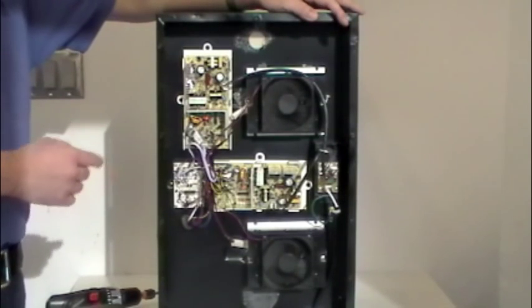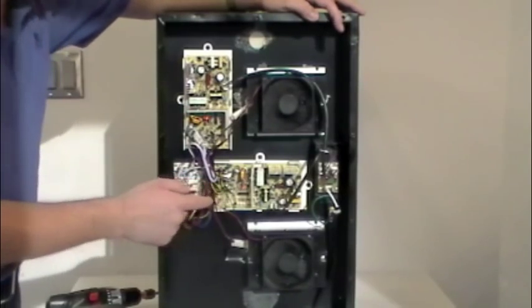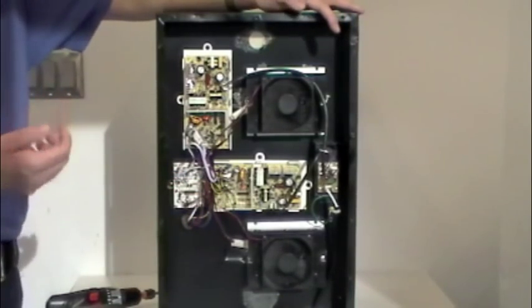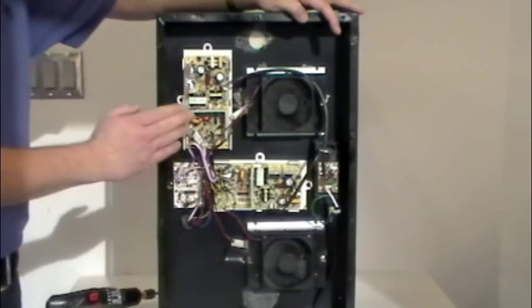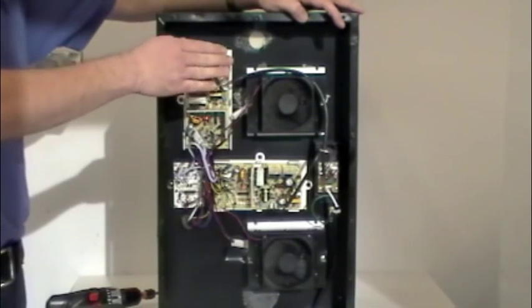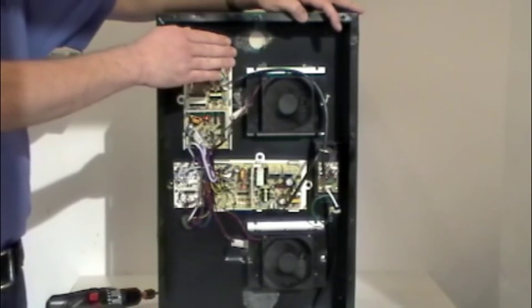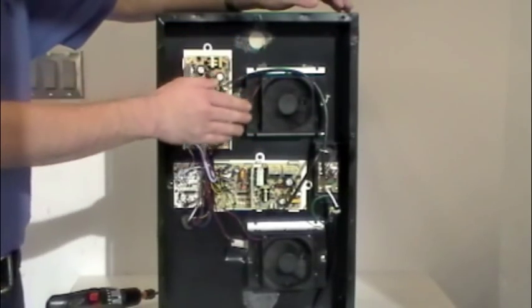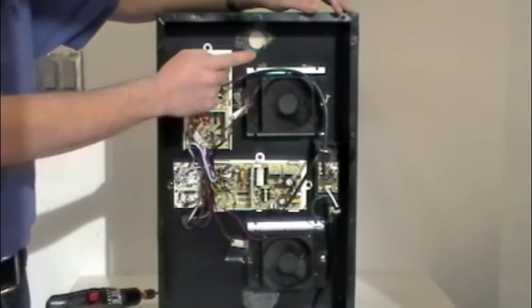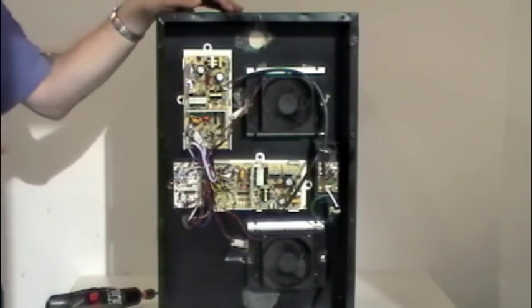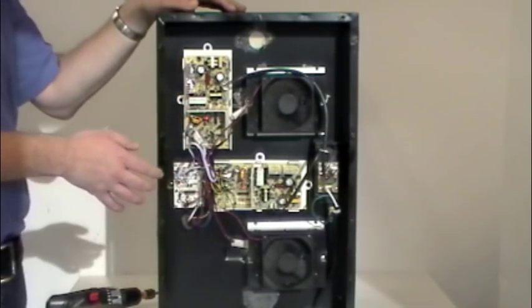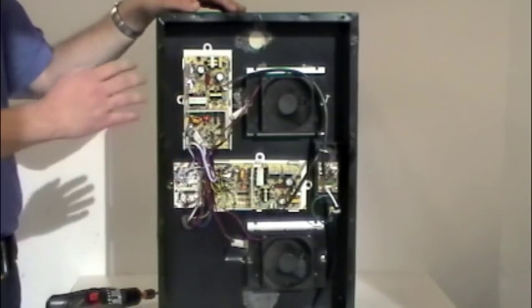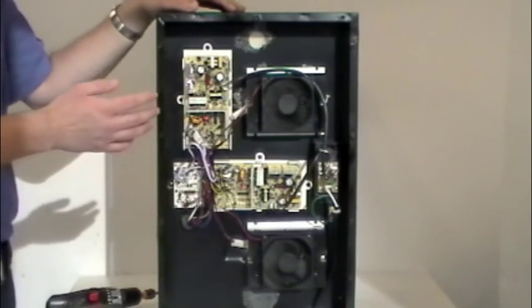We have 120 volts coming into the board that's being distributed. And we have 12 volts going out the other side, which go to the cooling nodes. Our green light here indicates that node activation is taking place. So we have our Peltier units, which is the official name of those cooling nodes. That indicates that 12 volts DC is being fed to each one of those. There is no self diagnostic capability on the boards other than you seeing power applied and node activation.